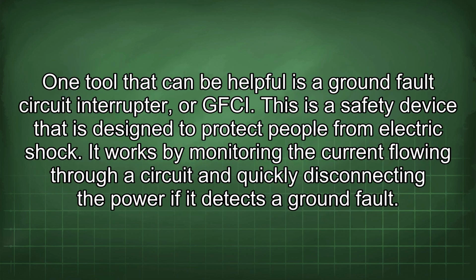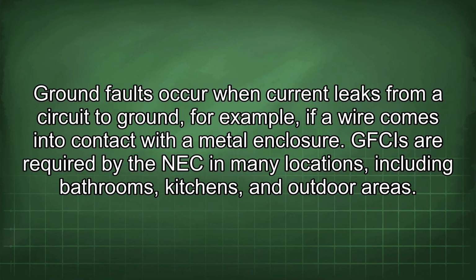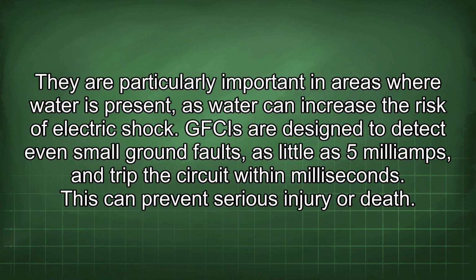One tool that can be helpful is the ground fault circuit interrupter, or GFCI. This is a safety device that is designed to protect people from electric shock. It works by monitoring the current flowing through a circuit and quickly disconnecting the power if it detects a ground fault. Ground faults occur when current leaks from a circuit to ground, for example, if a wire comes into contact with a metal enclosure. GFCIs are required by the NEC in many locations, including bathrooms, kitchens, and outdoor areas. They are particularly important in areas where water is present, as water can increase the risk of electric shock.